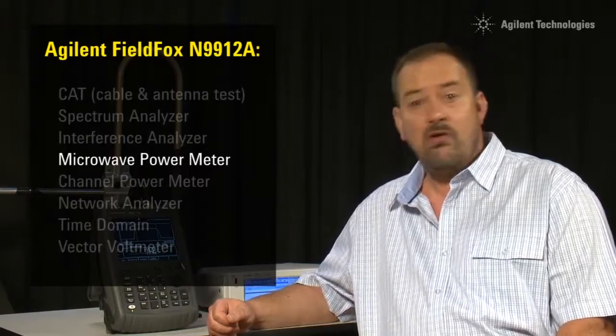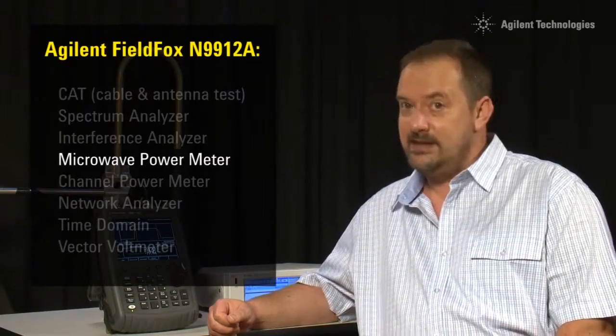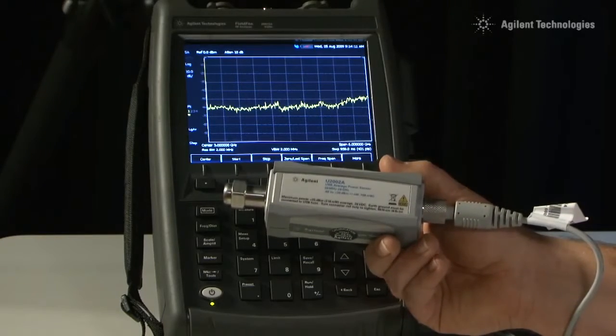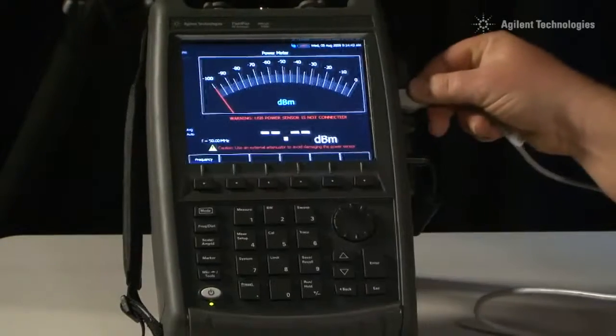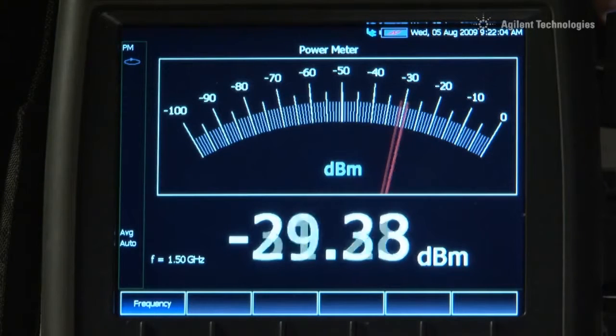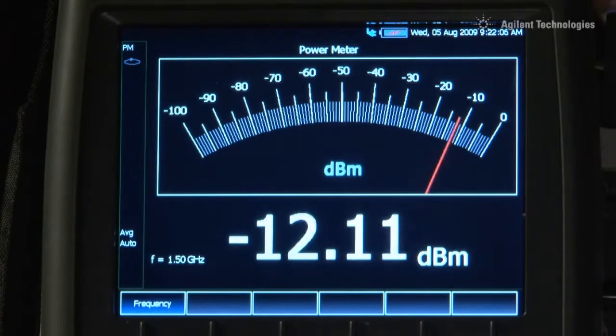If you need to make broadband power meter measurements with the ultimate accuracy, or make measurements at frequencies higher than 6 GHz, you can plug in any of Agilent's U2000 series of USB power sensors to make extremely accurate RF level measurements. Ideal for microwave fading applications, or aligning a satellite receiving dish.